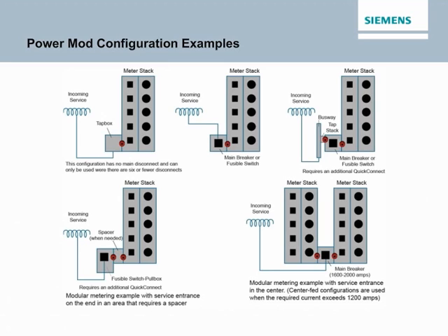Configuration 2 has a main breaker or main fusible switch, so this configuration permits more than 6 disconnects downstream from the main disconnect. Configuration 3 uses a tap stack to connect the configuration to a busway run. Configuration 4 uses a spacer. A spacer is commonly required between a meter stack and the main disconnect module, or tap box, for USERC installation. A spacer can also be used to extend the length of the lineup when needed.